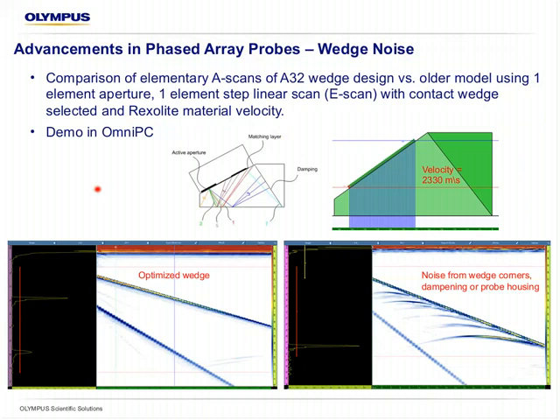In this slide, we're comparing the elementary A-scan of the A32 wedge design versus an older model using a standard setup that we use both to validate that the elements are active in the probe and the pulsers are active in the instrument. We do a one element step E-scan, meaning that every element has its own independent A-scan. There's no grouping them together, no beam steering, and no angle. We program the setup with a contact wedge, meaning no wedge, and we enter the material velocity for Rexolite. So in fact, we're essentially inspecting the wedge with a single element A-scan.